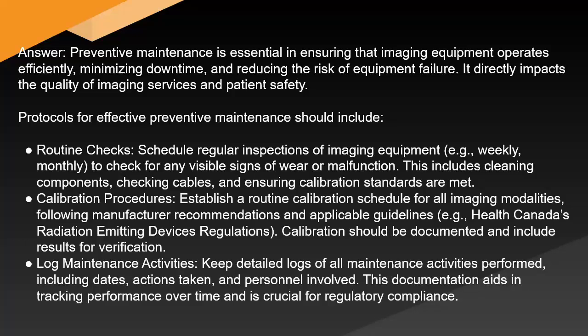Protocols for effective preventive maintenance should include routine checks: schedule regular inspections of imaging equipment, e.g., weekly or monthly, to check for any visible signs of wear or malfunction. This includes cleaning components, checking cables, and ensuring calibration standards are met.